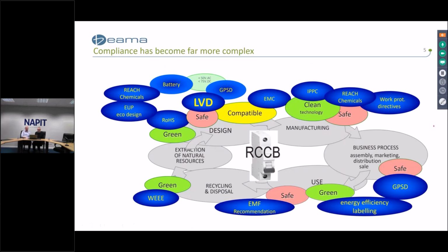So moving on towards the main topic of the webinar, RCDs, we just wanted to start with the background as to how product standards are developing. As you can see, compliance is becoming much more complex. To comply with the low voltage directive, and that's CE marking, there is an increasing list of requirements to take into account. The product standard in this case for an RCCB is BS EN 61008. And it's just one of the requirements.